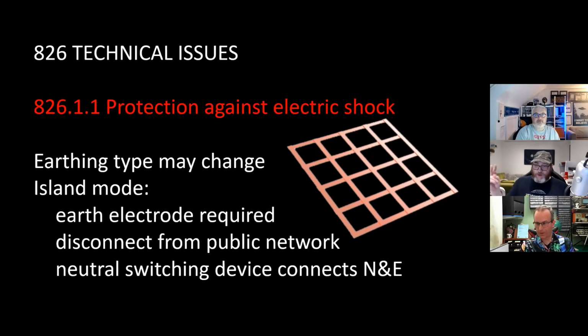So when you switch over from the normal incoming supply to your island mode, the device that isolates has to disconnect both live conductors simultaneously and at the same time connect neutral to earth. Yes. And the two switching operations can't overlap, so there's got to be a certain amount of space between them. It obviously can't connect neutral and earth while the grid is still connected, because that's not something we want to happen.